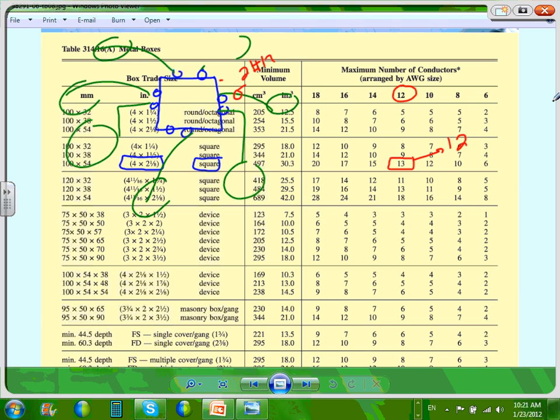You're absolutely right, because I need to drop one because I need a supply. So how many conductors did I need? Yep, because you need 2 for the supply. Then 1, 2, 3, 4, 5 fixtures. That's why if you limit yourself to a 4 from a J box like this, you're good.